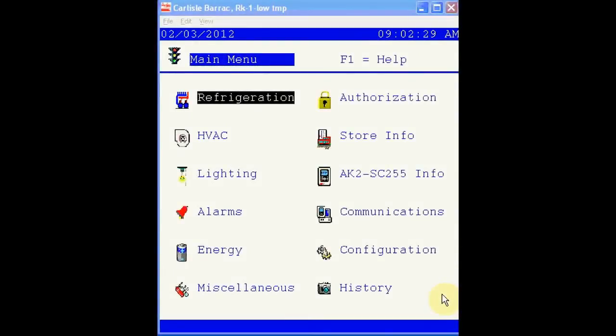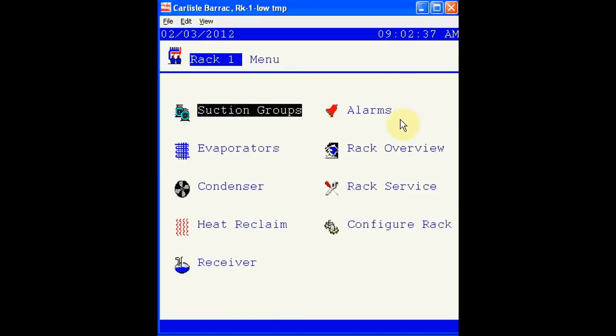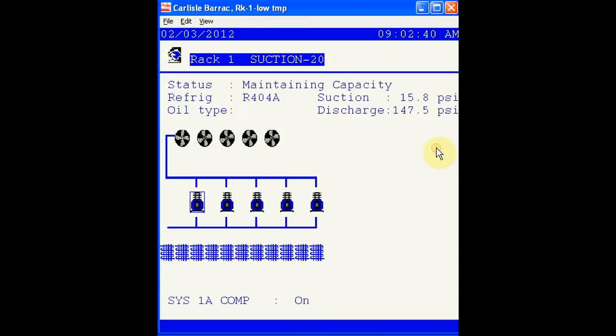It's possible to get an overview of the refrigeration system by first selecting refrigeration, the rack, then rack overview. This screen shows us the status of compressors, condensers, and circuits, along with displaying the refrigerant, oil type if programmed, suction pressure, and discharge pressure. Here you see the status of each condenser fan, compressor, and evaporator.